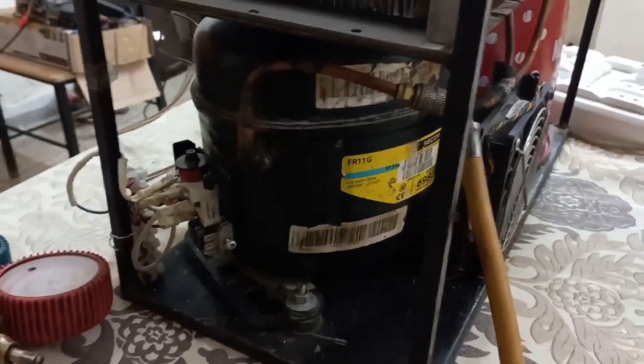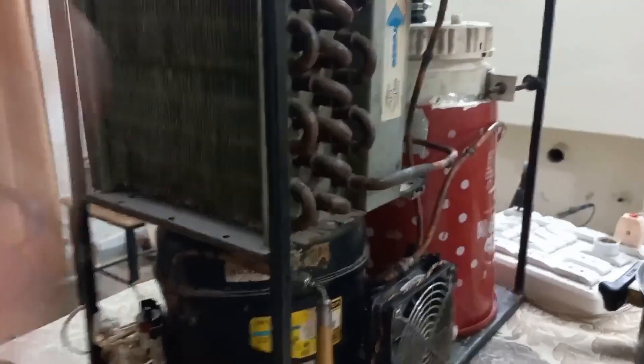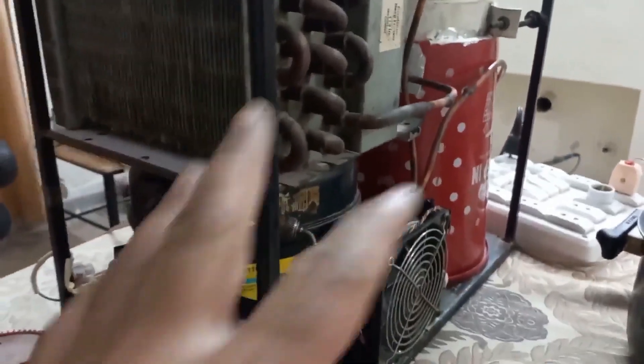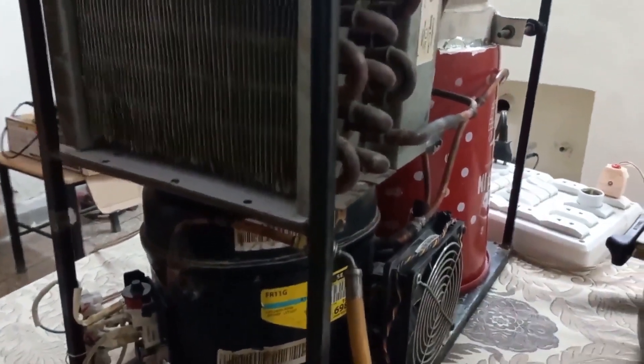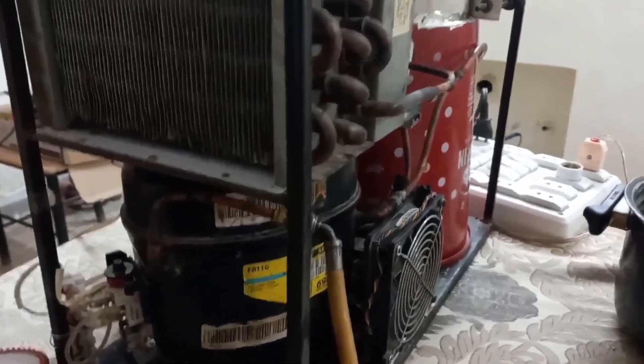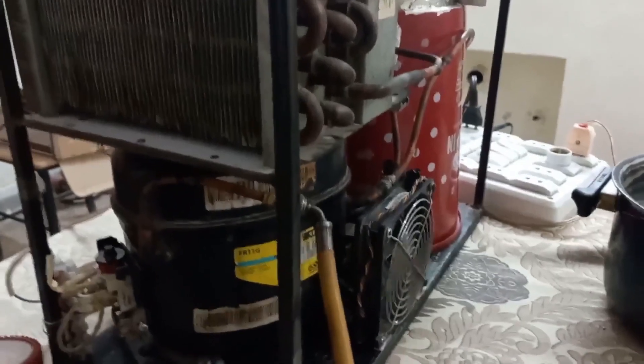If I charge less gas, then cooling will be less. This system — with this condenser, evaporator, compressor, and pipe length — works best with 260 grams of R134A gas. It can be plus or minus 270 or 250 grams as per ambient temperature and situation — a small plus or minus adjustment can be done.